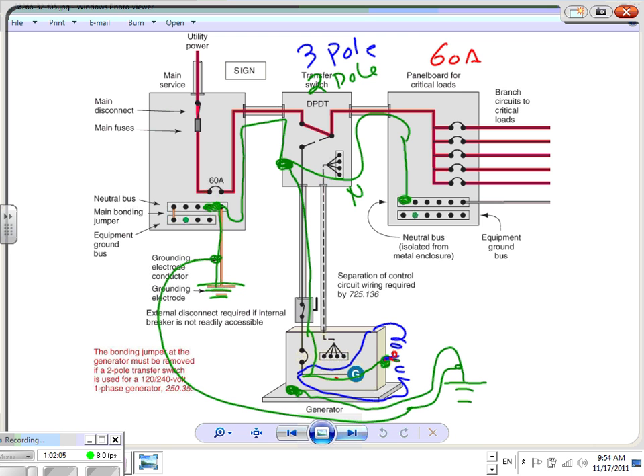Right in the panel, if you do it this way, there's two signs you have to put, by code. Sign number one, guys: you have to put a sign right here on the service. The sign right here should say, right at the service, that a second feeder feeds this building.